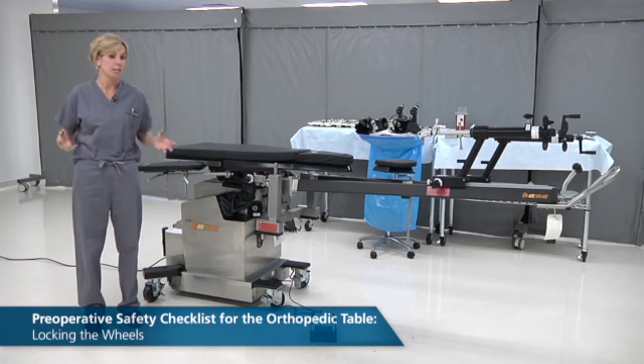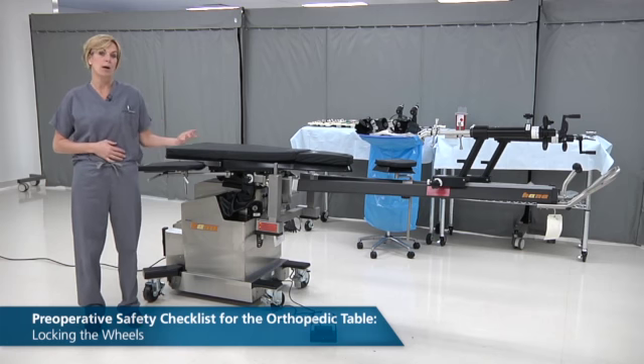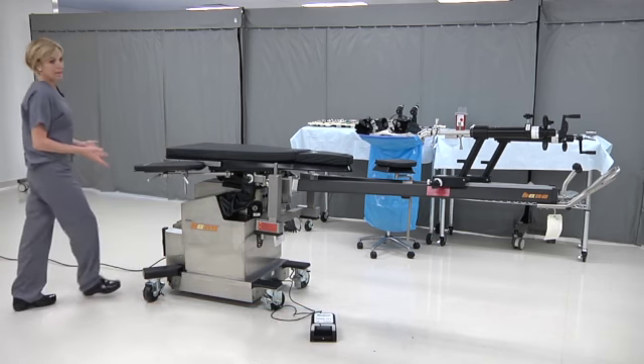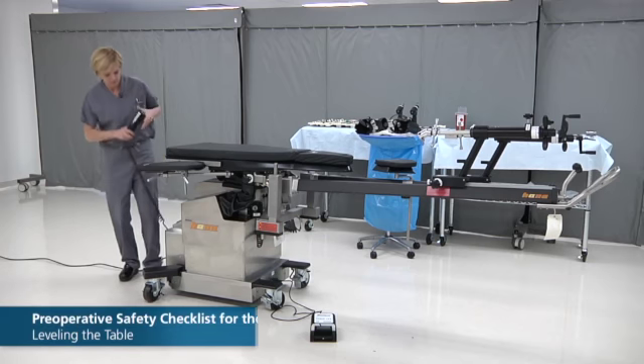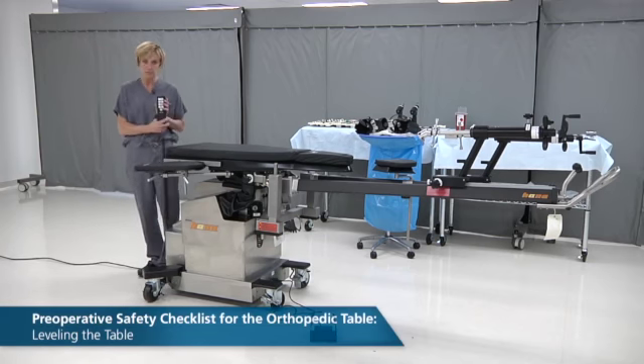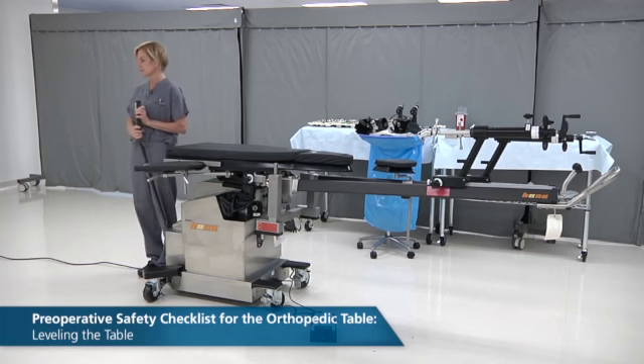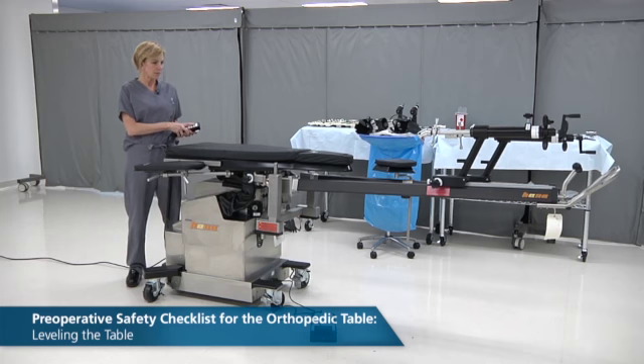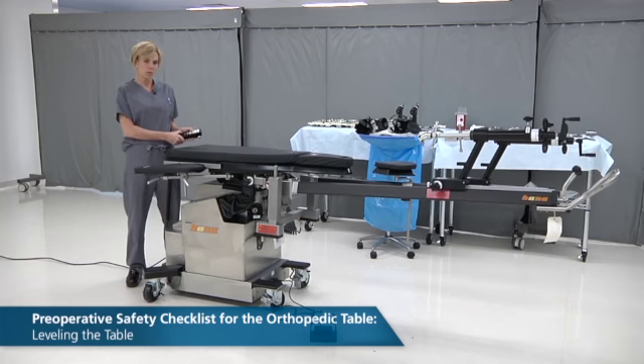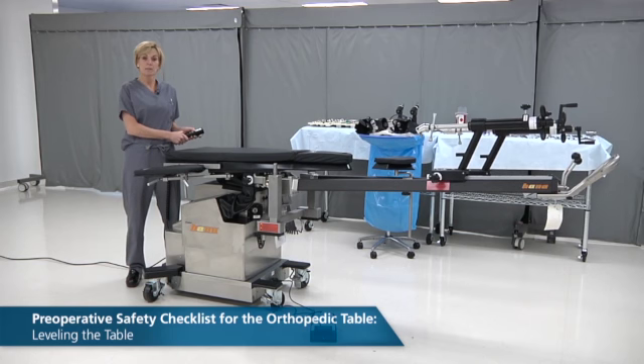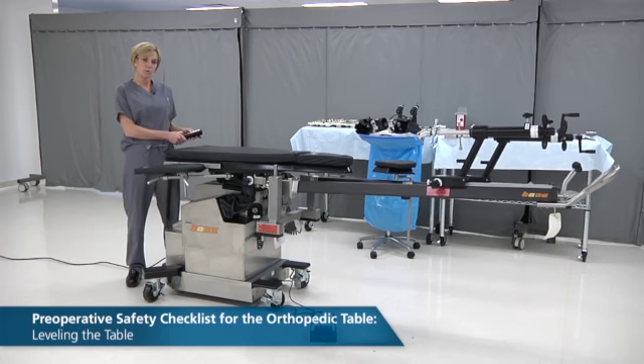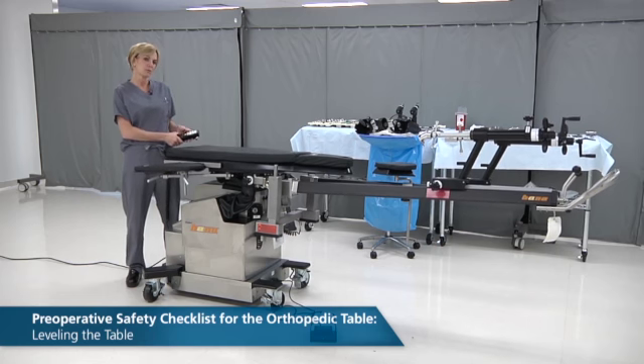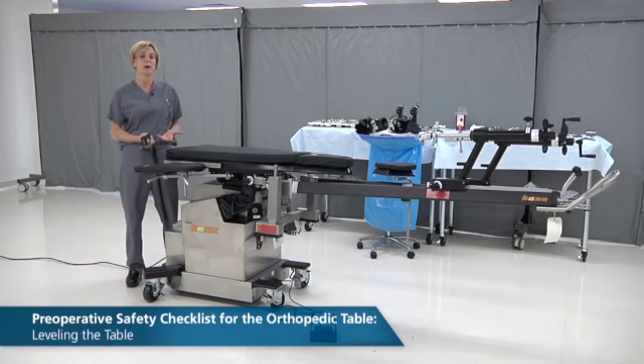make sure that the table is working, that it's plugged in, and that mechanically everything is going to be working during the operation itself. So where we're going to come to the head of the bed, there's a hand mechanical device here. The first thing I just do is push the return to level button. Now there are 7 buttons on this. The 7 buttons bring the table up and the table down, rolls the table, Trendelenburgs the table and does a reverse Trendelenburg, rolls the table to the left, and rolls the table to the right. So those are the 6 mechanical options that you have with this table.